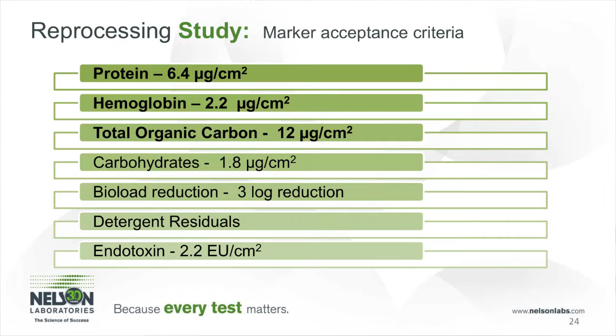Here I've got all of the acceptance criteria outlined, and these specific acceptance criteria mainly come from AAMI TIR 30. The bioload reduction is from TIR 30, but like I said, FDA does not necessarily need bioload reduction information at this point. And what the Bavarian government is requiring now is probably a 5-log reduction. That's what they're asking for. It's kind of hard to meet. And so they seem to be happy with a 3 to 4 in some circumstances, but they are specifying a 5-log reduction as well.